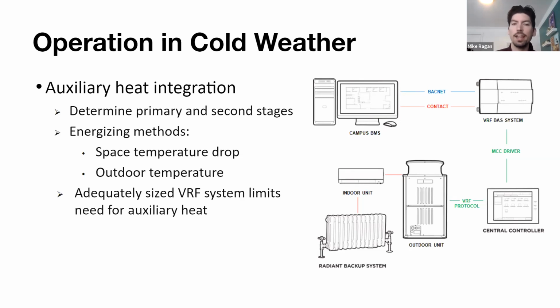But the one point I do want to emphasize is that if you size your VRF system accordingly, based on the design parameters that are given, that's seriously going to limit the actual need for that auxiliary heat system. We have dozens of installations across New England that have been designed with an auxiliary heat system that has never turned on. It's there, it's ready and waiting for the day it needs to turn on, but just based on the size of the VRF, based on the capabilities of that system, it was never really needed to turn on.